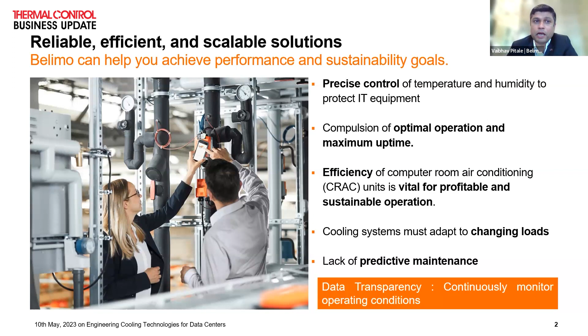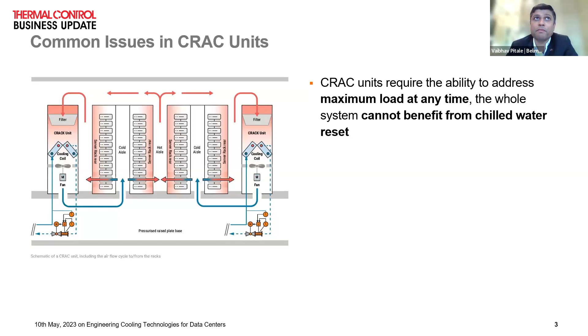There are other common issues with CRAC units. There is a maximum load at any point in time - you cannot do a reset on a chilled water system, because it can have an immense impact on the CRAC units. It's also important to look at criticality. We tend to over-select and over-commission the system because we want to build in redundancy, to ensure at any point in time we don't have an issue with any system not working.